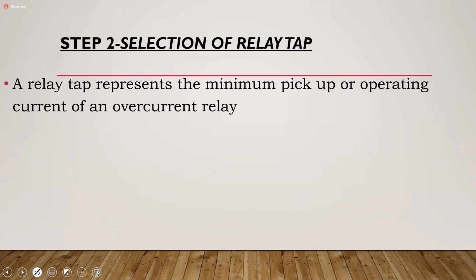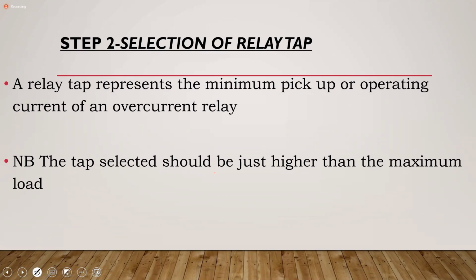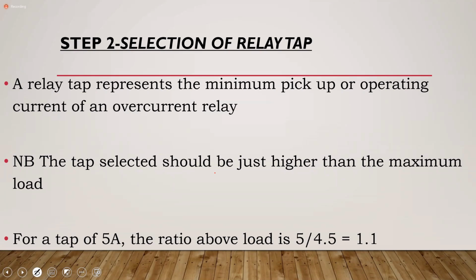Now the tap that you select will have to be based on what's available. Okay, you can't make up a tap, you know. You have to select what the relay has available. And we select the tap to be just higher than the maximum load, because you can have a slight overload. There's nothing wrong with that. As I was explaining earlier, you may be doing switching operations and you transfer loads from one circuit to the next. But of course, that would not be there permanently. So you want to allow for slight overloads. So you select the tap to be just higher than the maximum load. In this instance, I'm going to select a tap of 5.